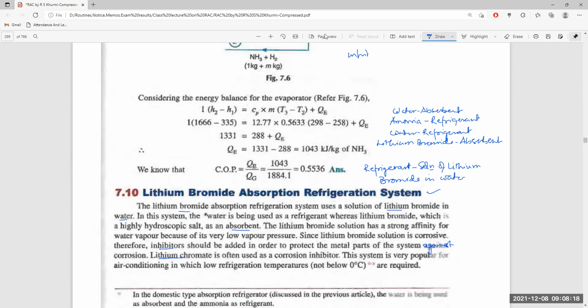Inhibitors are chemicals protecting against corrosion. Water is the refrigerant, and lithium bromide is the absorbent. Now, it is very popular for air conditioning where refrigeration is required not below 0 degree centigrade. So, more or less around 0 degree centigrade refrigeration is there, so it is usable, far better usable.